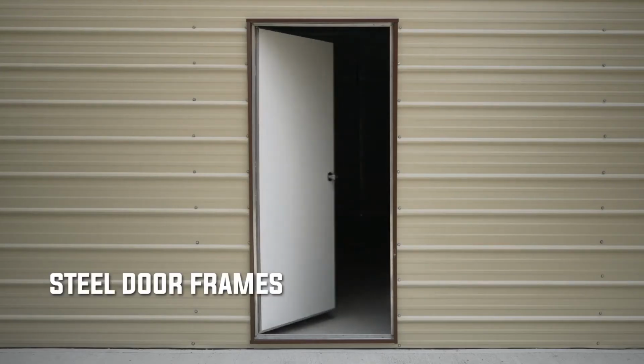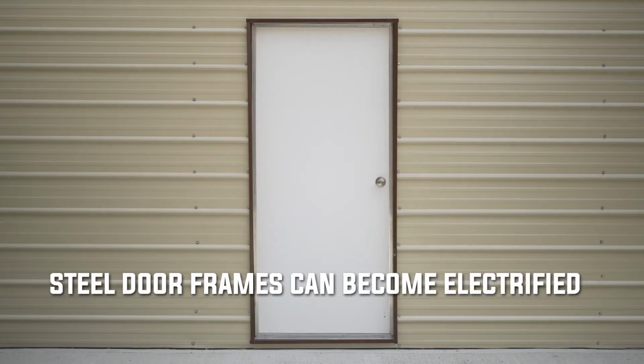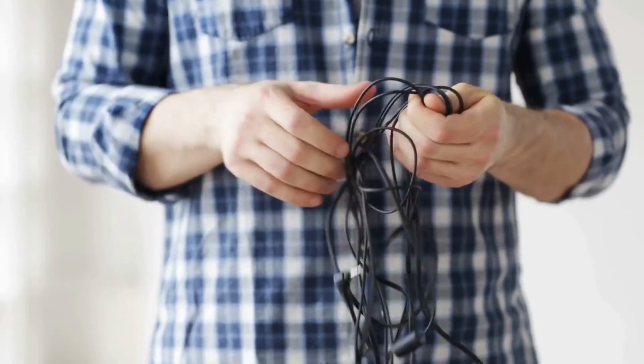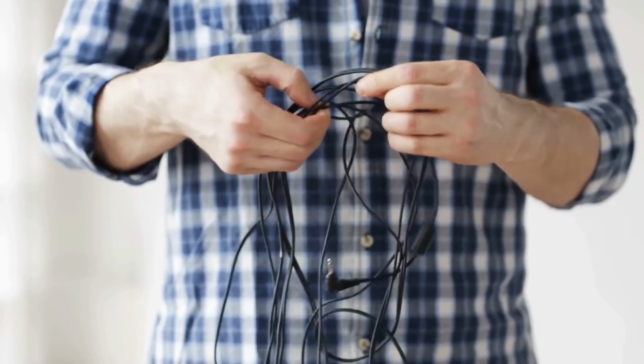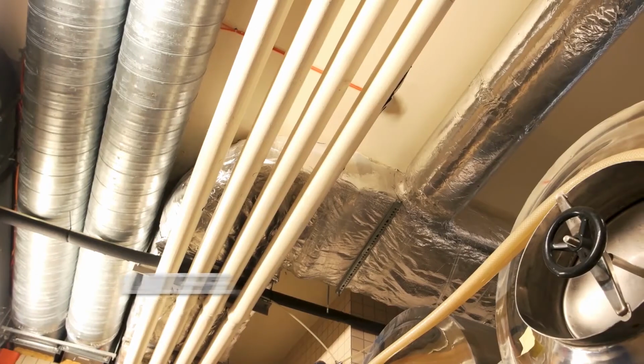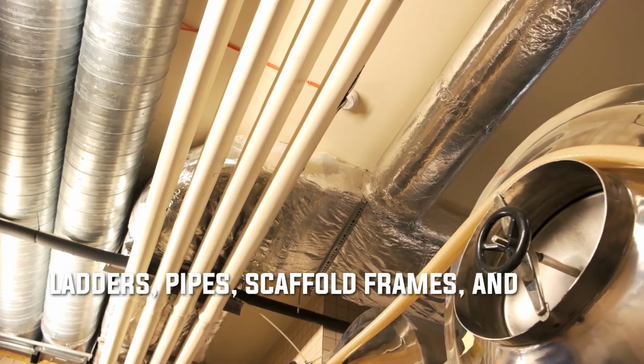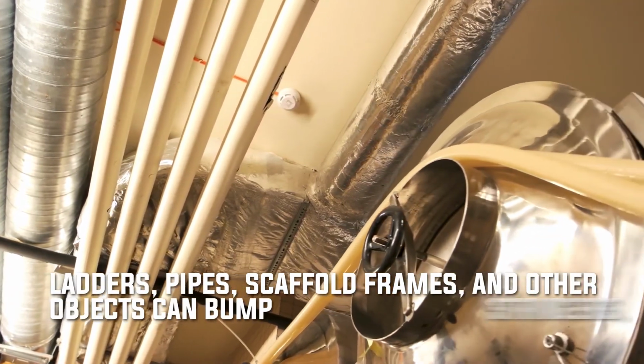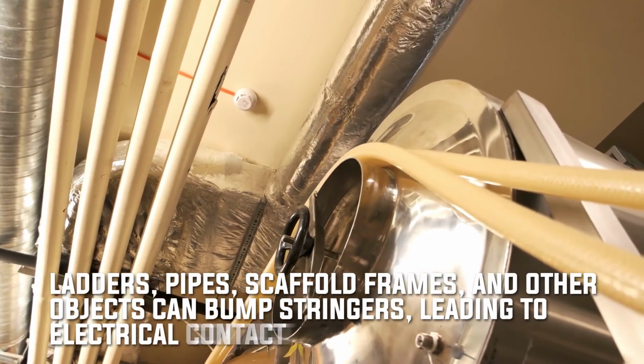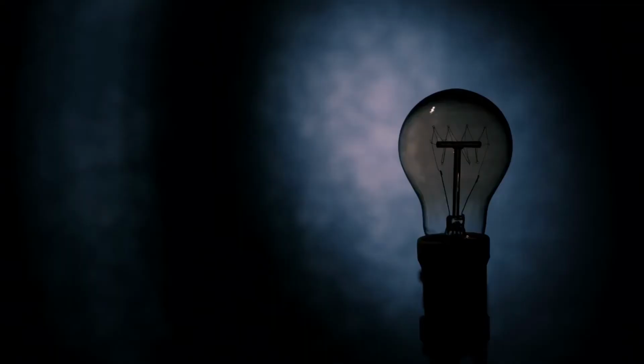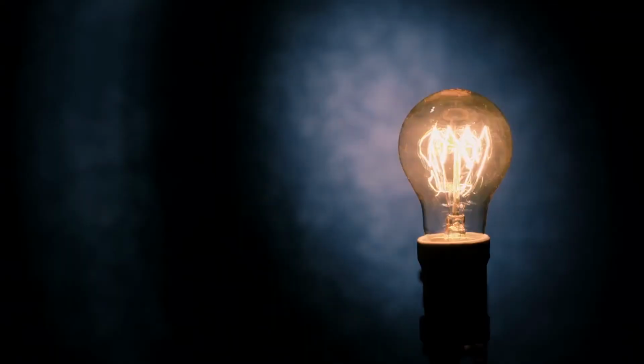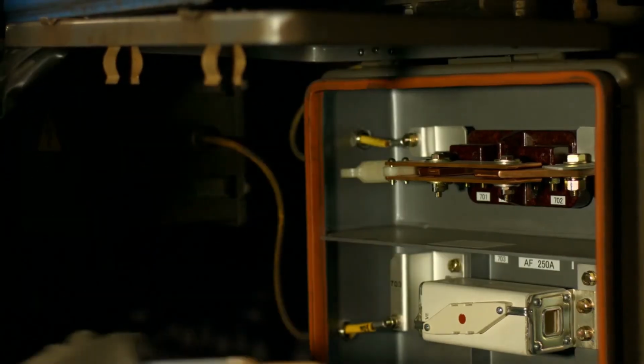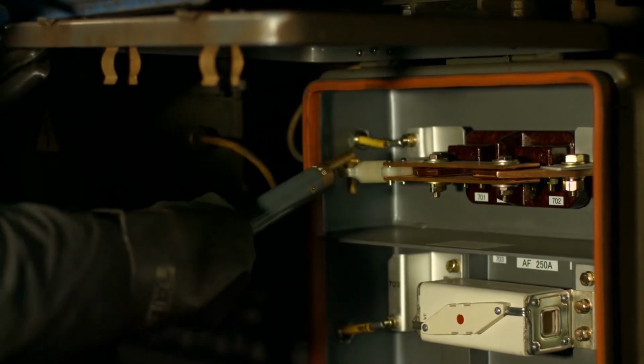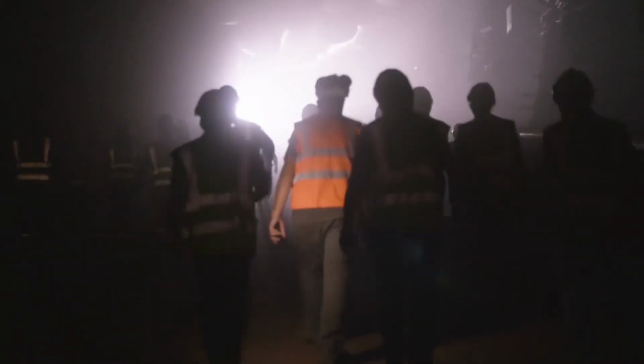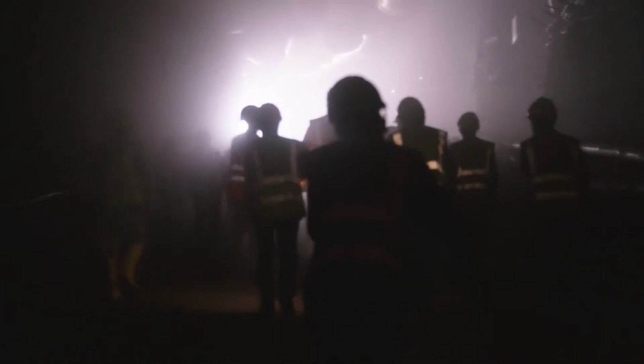Steel door frames can become electrified when doors close on wires. Temporary lines often pass through doors and may accidentally close on them. Ladders, pipes, scaffold frames, and other objects can bump stringers, leading to electrical contact and shock. Lastly, dead, missing, or low wattage bulbs, inadequate power, and blown fuses can leave stairwells, basements, and other areas poorly lit or with no lighting at all, increasing the risk of injury.